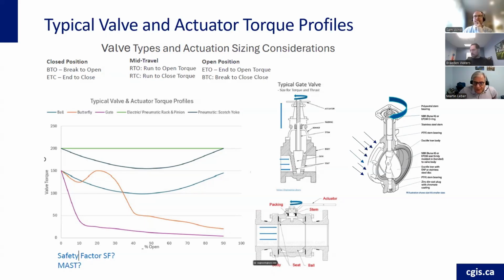Typically, valve actuators, and there are all different kinds, you can get extended duties, but typically you get 15 minutes at a 20 or 30% run. Different manufacturers have different percent run factors. Limitorque typically has a 30% run for the electronic series and 20% for the conventional hardwired actuators. We'll get into that a little bit in the presentation. What that means is that for a period of 15 minutes, if you run at 20% of the rated torque, the actuator will not overheat. It's really a matter of not overheating the motor, because there's a thermistor that will trip and stop it. On applications where there's a long stroke time, you really have to be careful about that.